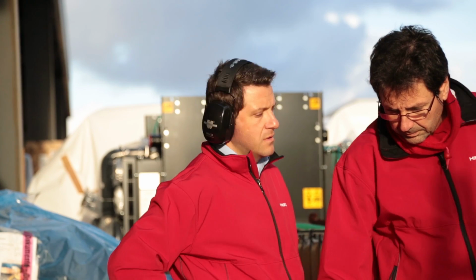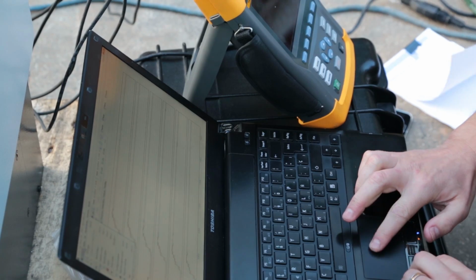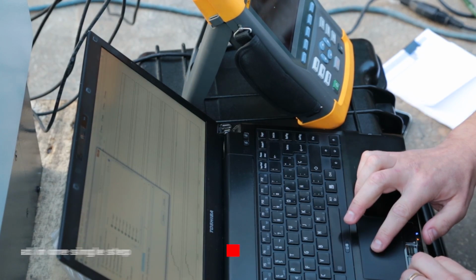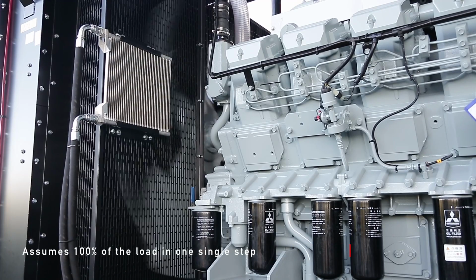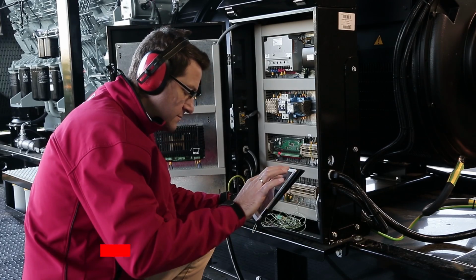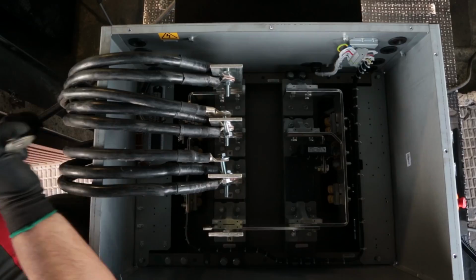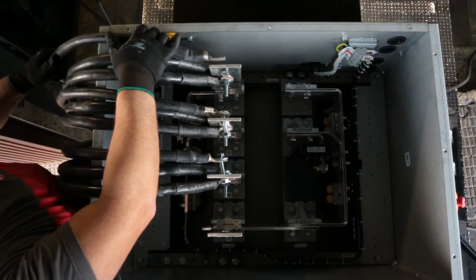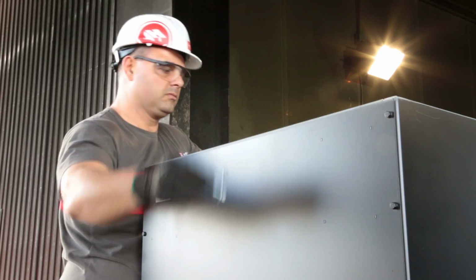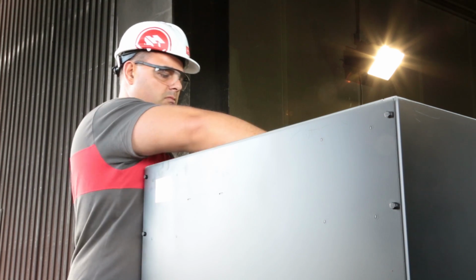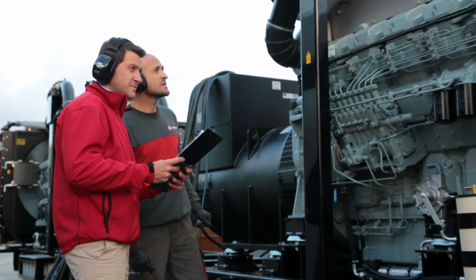We have chosen controllers that can manage a synchronization technique known as dead bus. When gensets are started, the load breakers are already closed to the common bus bars and the excitation fields are disconnected from the AVRs. Once engines are running, the excitation fields are connected and the alternators start to share the load.